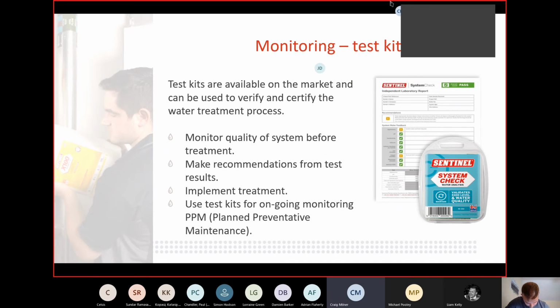How do you know you've treated the system correctly? We recommend a system check. This is a sample. You get a sample of the mains water and a sample of the system water. When you're taking the sample, always let the water run out of the valve, the test point on the return, a little, so you get about a litre out, so that any debris in the bottom of that valve is flushed out before you take your sample. Then fill the form in, send it off, and you get a lab report back, which will tell you, yep, you've done everything right, everything's within balance, and there's a nice document that you can put into your O&Ms and pass over to your client and say, we've done our part right.